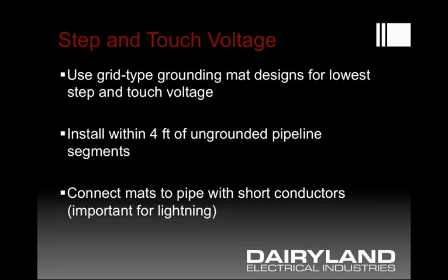The mat doesn't need to cover everything within a fence, but it does need to be within the region where anyone could reach the pipe and contact it. Don't forget the principle about inductance: connecting the mat to the pipe must be done with short conductors, otherwise we raise the touch voltage a person would be exposed to. The step voltage may not change, but the touch voltage would be unnecessarily increased.